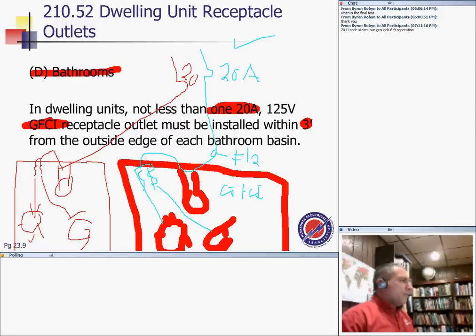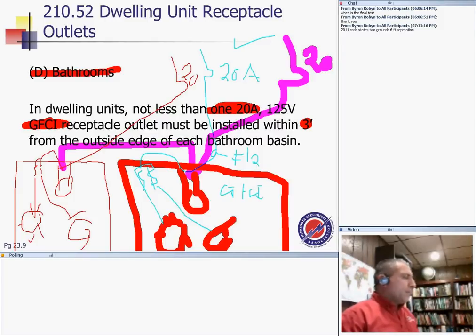So if you don't feed the fans, why would you do that? But they allow you, if you don't feed them, to go from this receptacle to this receptacle, out of here to a 20 amp circuit. That 20 amp circuit feeds only the receptacles in the bathrooms. If you're feeding more than one bathroom, you only limit it to the receptacles. If you feed one bathroom, you can feed everything in that particular bathroom, especially the exhaust fan and the receptacle. Any question, guys? Question about that?